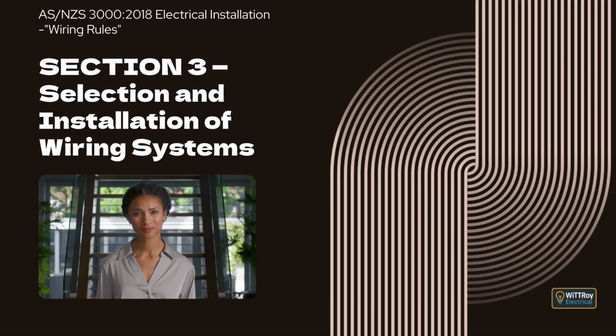Clause 3.10.3.4 Bending. This clause explains that bends in wiring enclosures must be made so that cables and conductors are not damaged. In rigid conduit, bends must not significantly reduce the internal diameter. Where direction changes occur in trunking or ducts, the arrangement must still allow cables to be bent without damage, and the cable bending requirements of Clause 3.9.6 must be met. Clause 3.10.3.5 Passage of conductors. This clause explains that conductors and cables passing through enclosures or openings must be adequately protected. Openings must be of suitable size and fitted with securely fixed bushes, or otherwise be free of sharp edges that could damage insulation or sheathing.